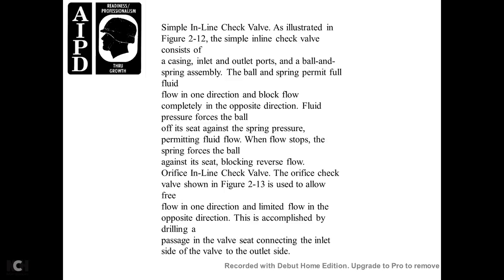Simple Inline Check Valve. The simple inline check valve illustrated in figure 2-12 consists of a casing, inlet and outlet ports, and a ball-and-spring assembly. It permits fluid flow in one direction and blocks flow in the complete opposite direction. Fluid pressure forces the ball out of the seat against the spring pressure, permitting fluid flow. When flow stops, the spring forces the ball against the seat, blocking reverse flow. Orifice Inline Check Valve. The orifice check valve shown in figure 2-13 is used to allow free flow in one direction and limited flow in the opposite direction. This is accomplished by drilling a passage in the valve seat connecting the inlet side of the valve to the outlet side.